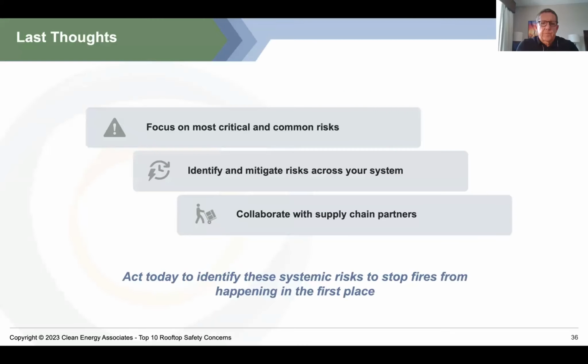So closing out, we wanted to talk about mitigating performance risks and safety risks. The issue is 97% of sites have these risks. What we recommend is that your teams do a deep dive on the baseline to prevent this from happening again, get an assessment of what you have. Not knowing what you have means not knowing if your terminations are good. At least if you've inspected it, you know whether it's good or bad, and you can make decisions based on that.